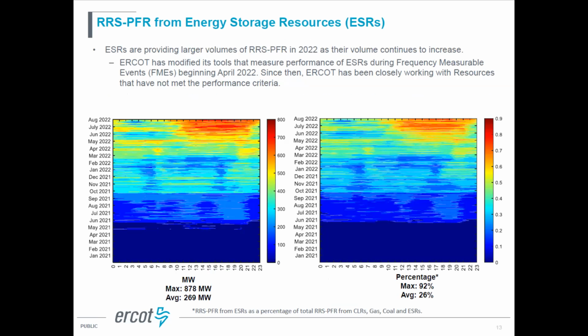As we continue to add more batteries to our system, because of their economics, load resources are price takers for the response reserve. But we have seen those batteries already take over market share from the generation resources to provide response reserve. During those hot summer days this past summer, those batteries could provide about 800 or 900 megawatt of RRS PFR, and the rest of the response reserve obligation is fulfilled by the faster response load resources. In terms of percentage, it is almost 80% or 90%, because of the economic advantage of the battery over those synchronous machines.